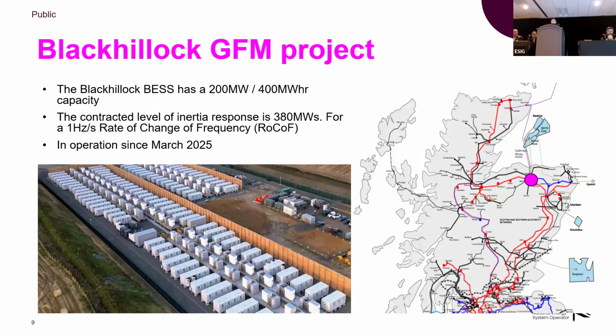So let's concentrate on our first battery project, the grid forming battery project under the procurement of the stability services. This is a project commissioned, I think, in March this year. It's connecting to a Blackhillock substation in the northern part of Scotland. Within that area, we have a large concentration of renewable generation, including all the offshore wind, and we also have an HVDC connected into that area. In general, the IBR concentration level is fairly high in that area. We don't have many synchronous machines left, and traditionally we have had stability issues in that area, especially around subsynchronous oscillation.